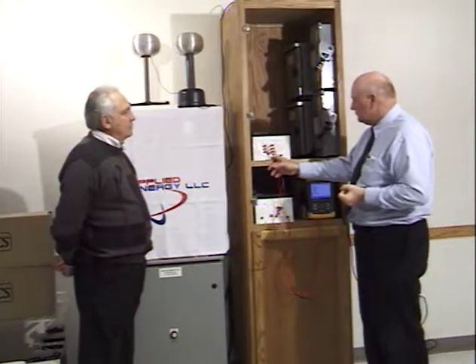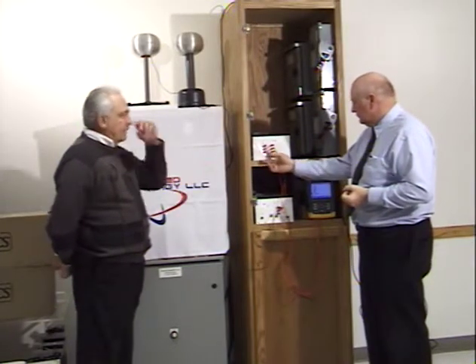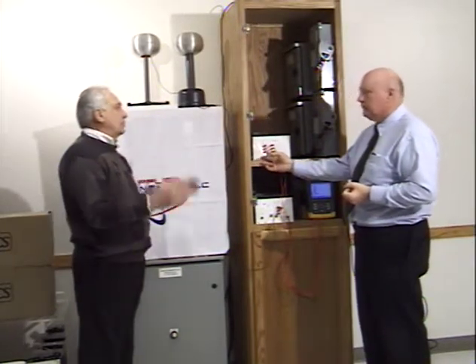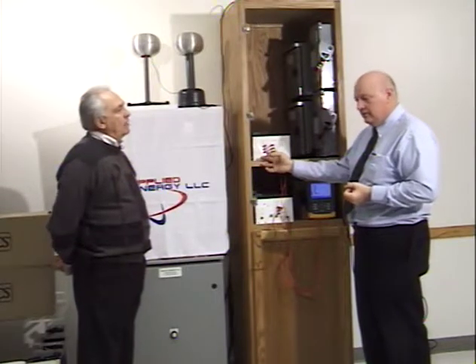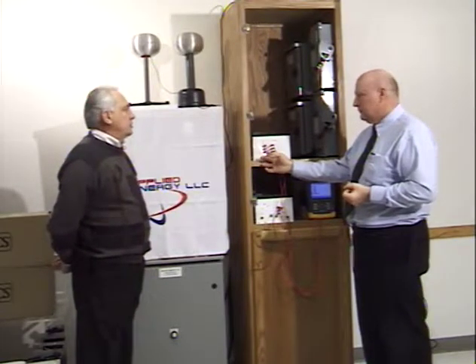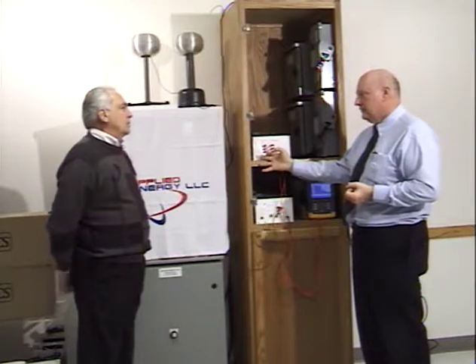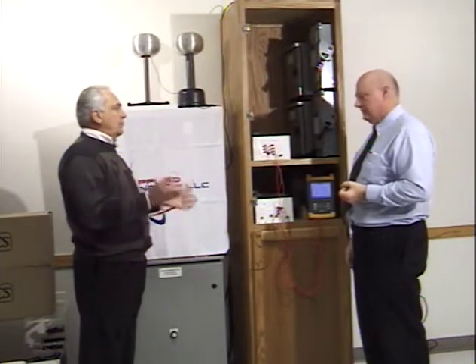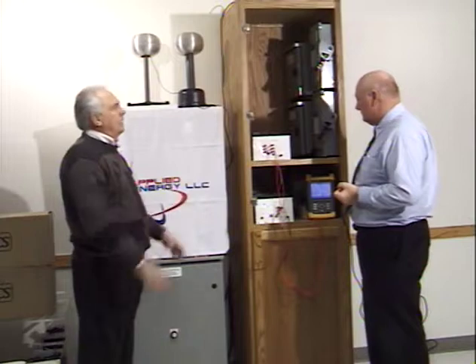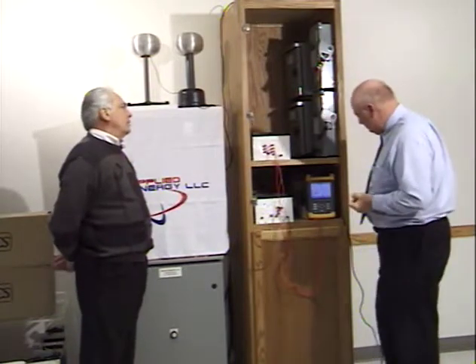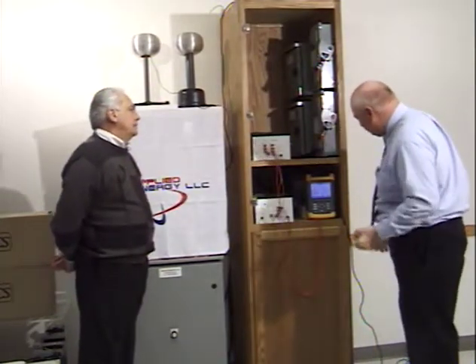Now, I understand some of the people have actually tried to put ceramics at the end of the shaft of that motor to try to minimize that damage to the bearings. However, that metal of the shaft and that ceramic have actually a different temperature coefficient as far as expansion and contraction. So I don't imagine that really holds up too well, does it? No, not too well.